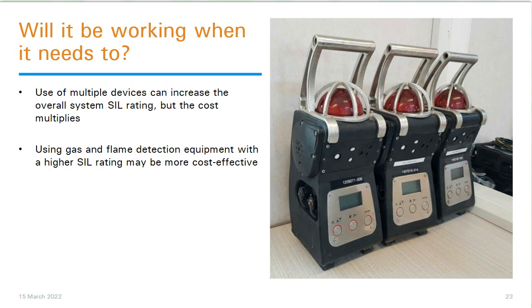But that can be quite expensive. Buying 2 pieces of equipment is clearly more expensive than buying 1, and buying 3 is an additional cost. So the other way to improve the SIL rating is to buy equipment that has a higher SIL rating. It's one or the other. Both are perfectly valid ways of achieving a good SIL rating for the area gas detection. Buying better equipment or doubling up.